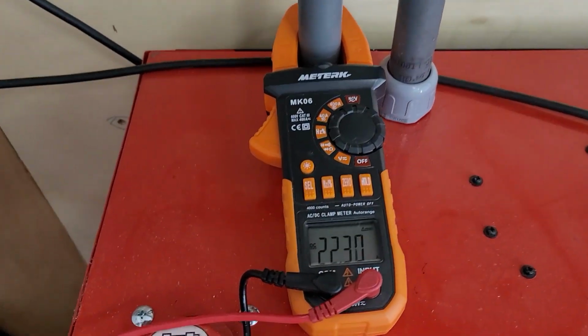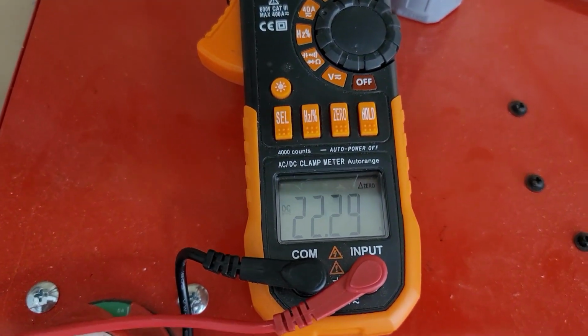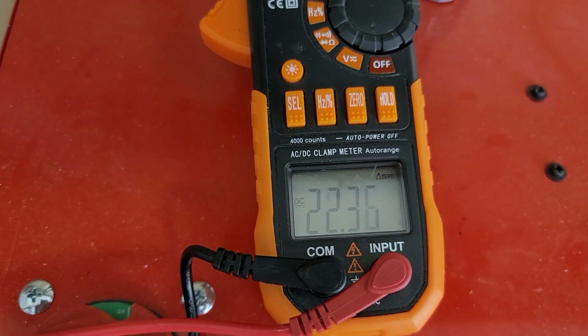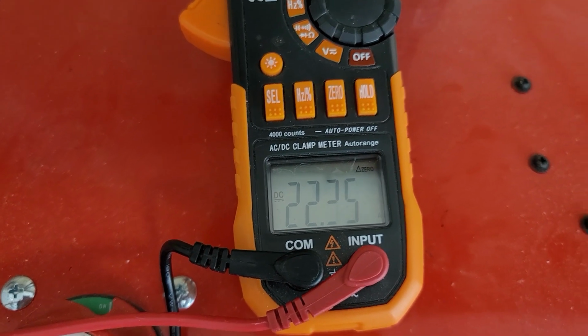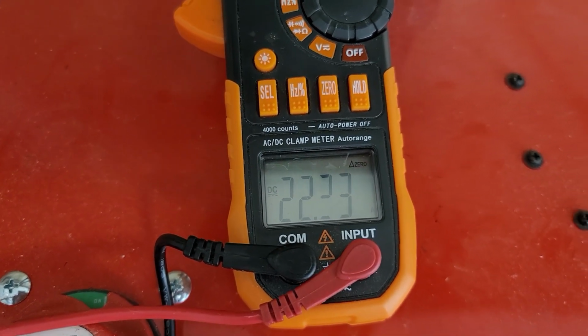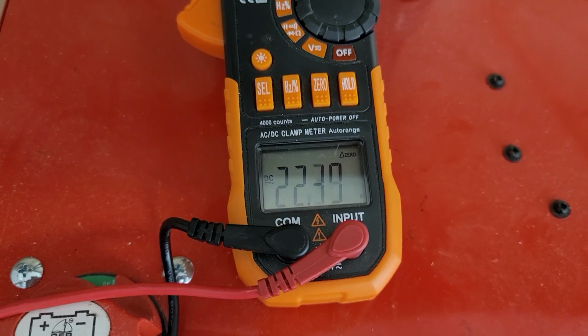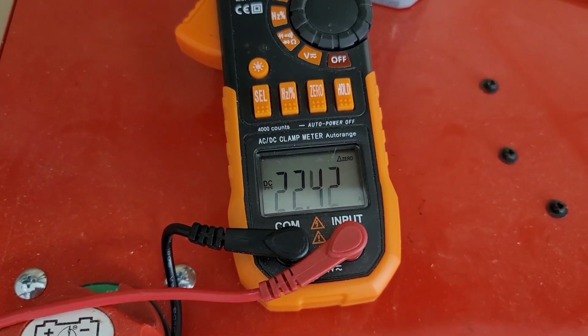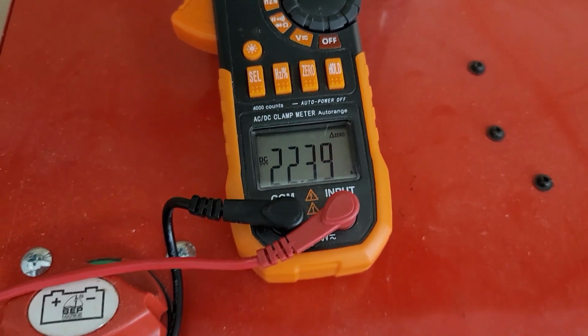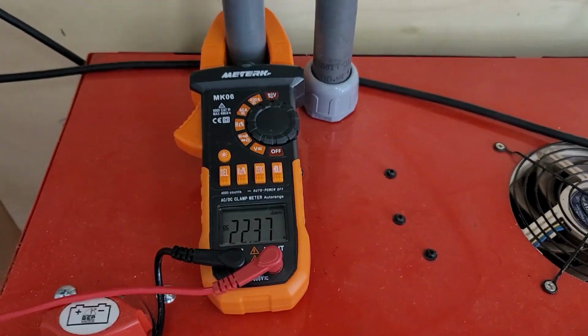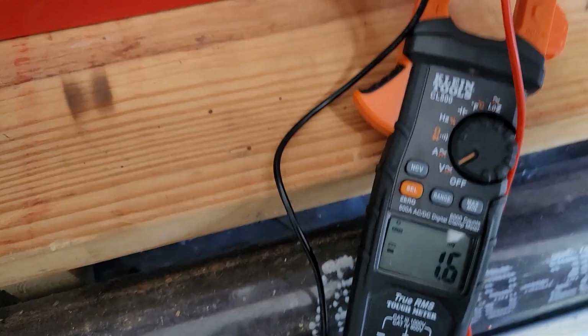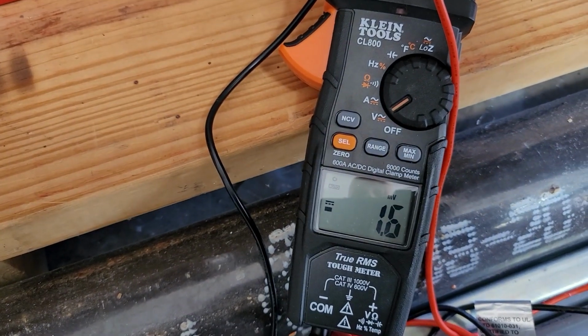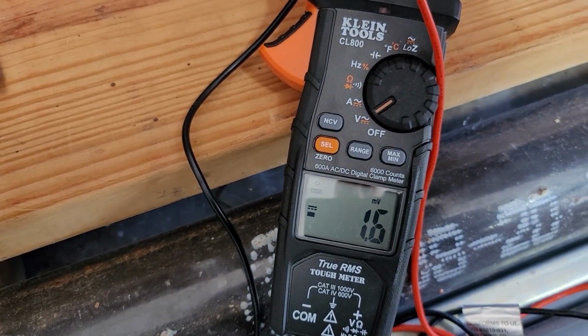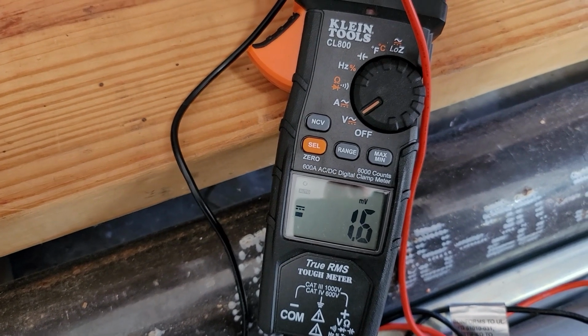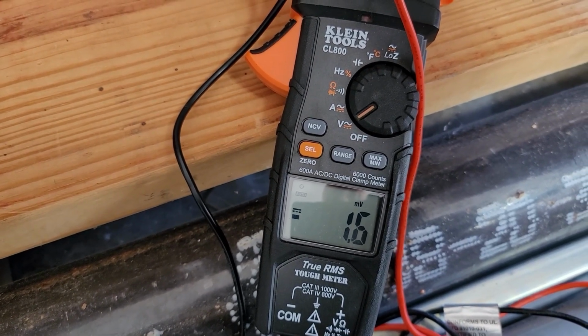Right now this Powerwall is being charged at 22 amps. Let's check the voltage drop across this connection at this amount of amps. At 22 amps, we have a 1.6 millivolt voltage drop across this connection.